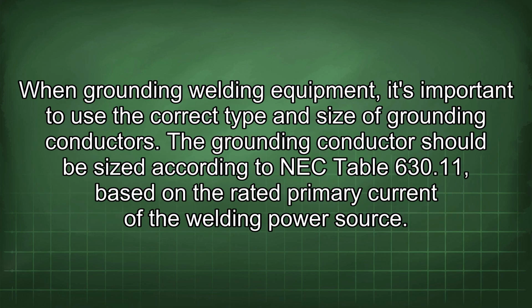When grounding welding equipment, it's important to use the correct type and size of grounding conductors. The grounding conductor should be sized according to NEC Table 630.11, based on the rated primary current of the welding power source.